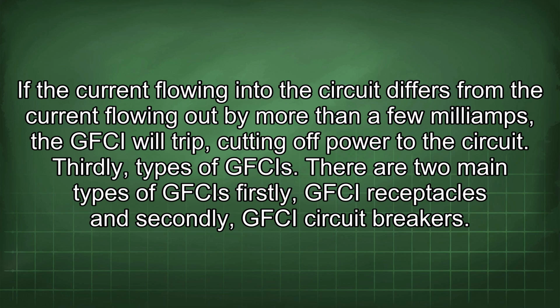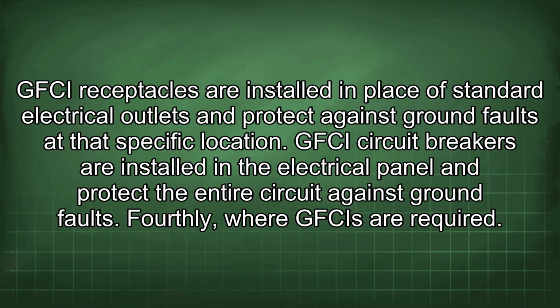Thirdly, types of GFCIs. There are two main types of GFCIs. Firstly, GFCI receptacles, and secondly, GFCI circuit breakers. GFCI receptacles are installed in place of standard electrical outlets and protect against ground faults at that specific location. GFCI circuit breakers are installed in the electrical panel and protect the entire circuit against ground faults.